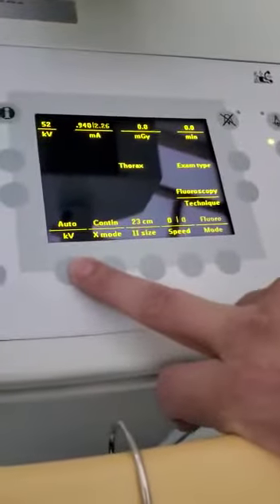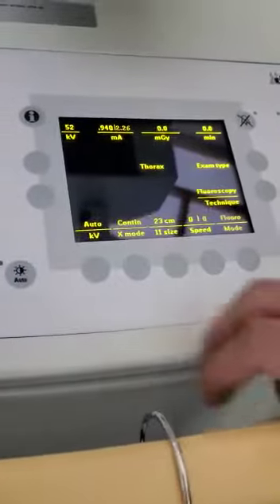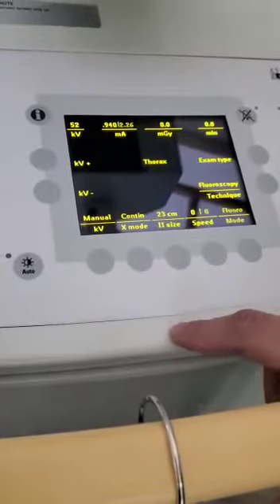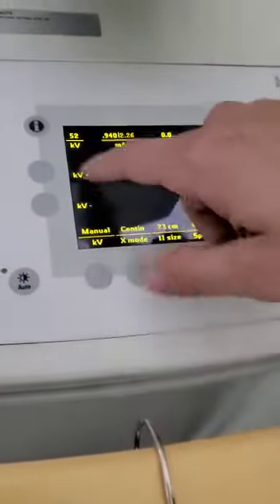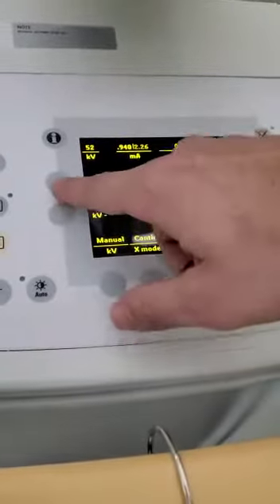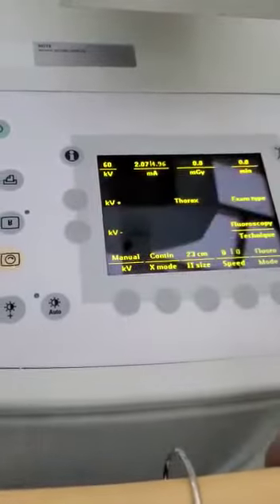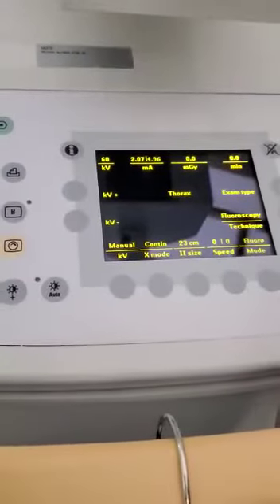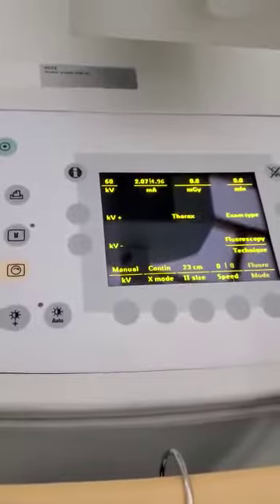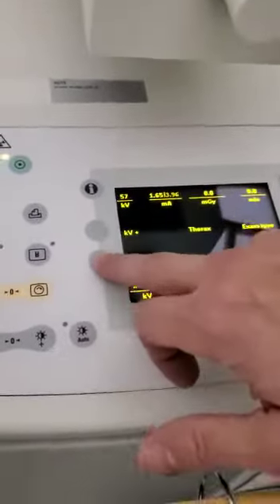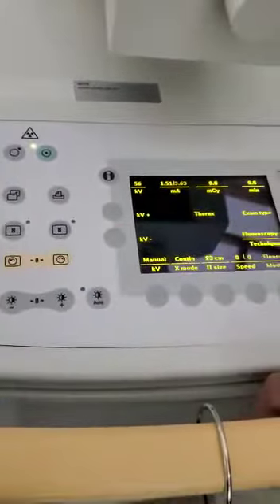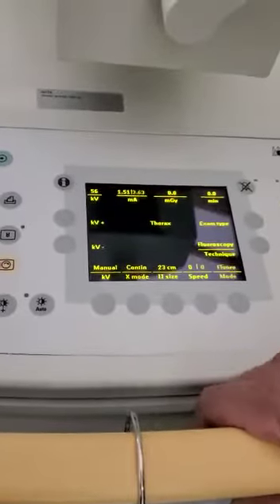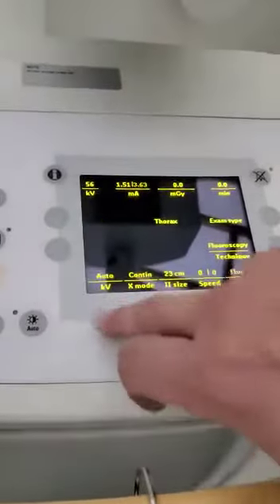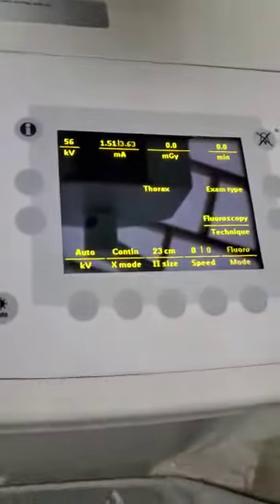Your system automatically releases the dose required for the preset, but if you ever have a larger patient and you need to penetrate more and you need to up your KV, that's done here. You hit auto, it turns it to manual. You're going to hit the KV plus button, which increases your radiation or output, which allows you to get a brighter and more powerful image so you can penetrate if needed. Now, usually, with what you guys are doing, you will not need to up the KV in high definition fluoro. But if you do ever need to do it, it's there.